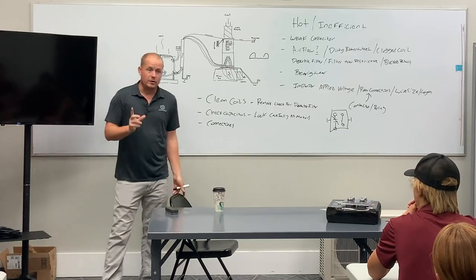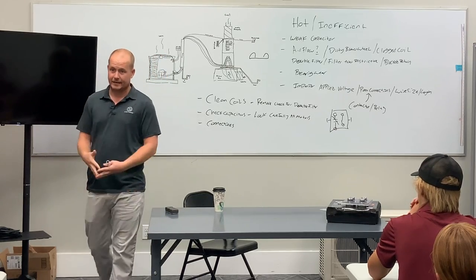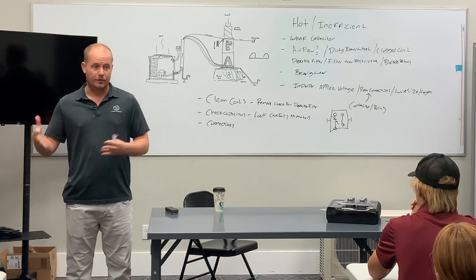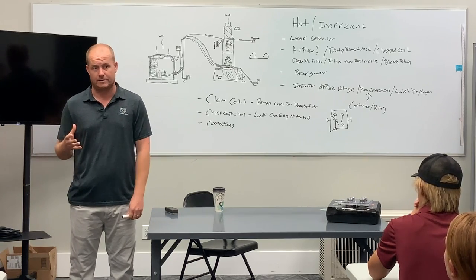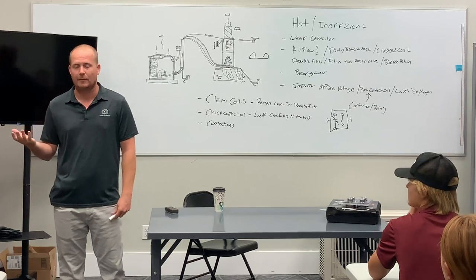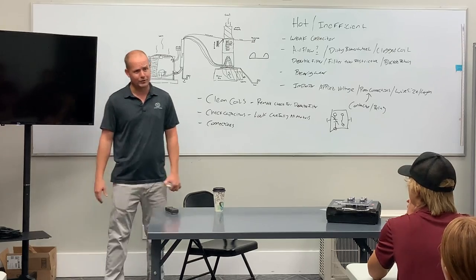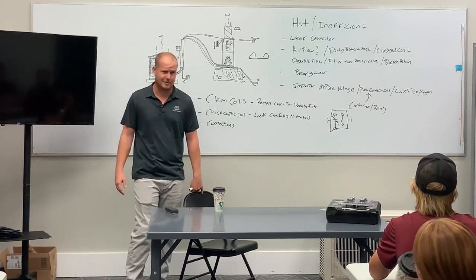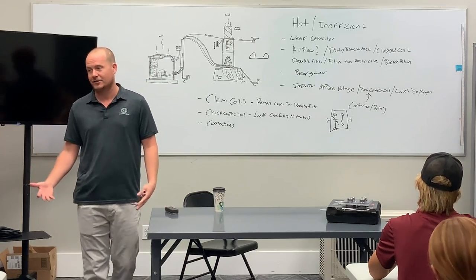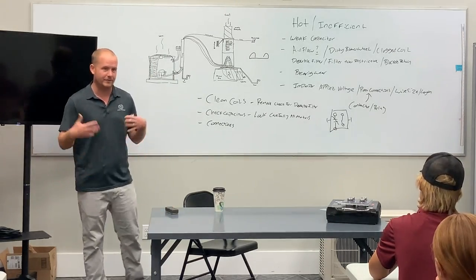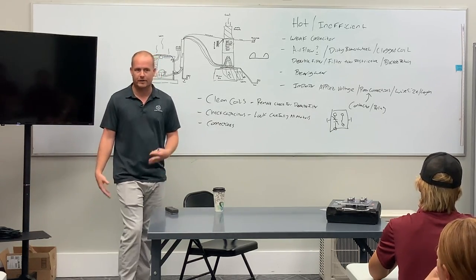So on this note, when you have high voltage coming into an air handler that was done improperly, connected poorly, quote the customer to redo that. That is one of the single greatest fire hazards in a customer's house, very realistically. Now, we don't say that to the customer. We are not going to use scare tactics, like, do you care about your children? Well, you better get this fixed right away because your house is about to burn down. That sort of hyperbole is actually somewhat common in our trade, but we don't do that. But when you find something like that, point it out, quote the customer to redo it.